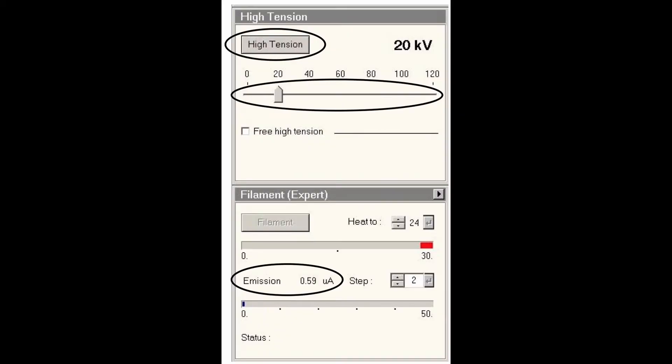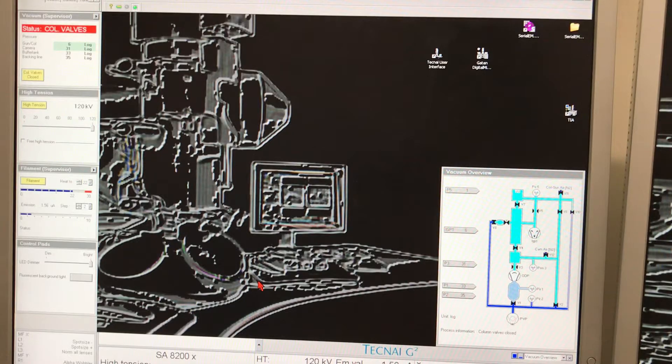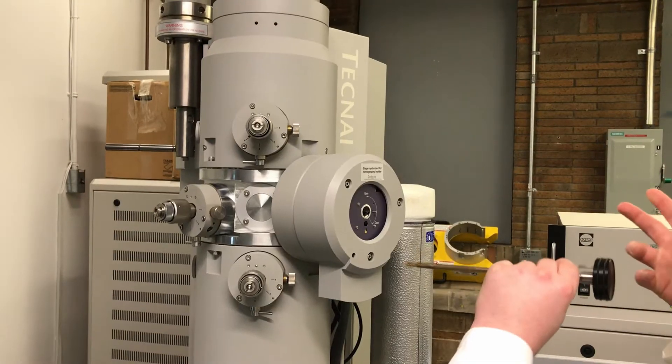The second box below is for the high-tension tank, and the high-tension tank button should be in yellow and should read 120 kV. The last thing below it is the control for the filament, so the filament button should also be in yellow so it can start emitting electrons.